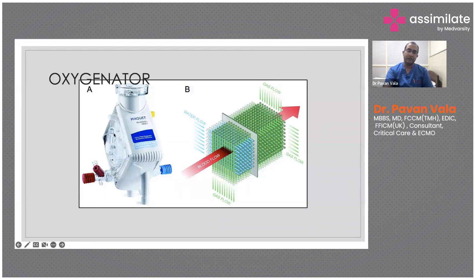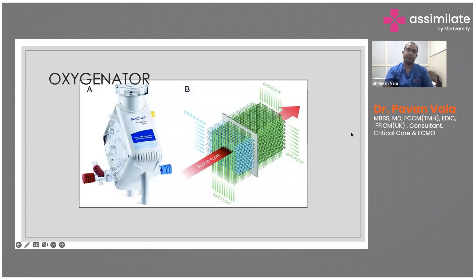The oxygenator is made of PMP — polymethyl pentene — a hollow fiber oxygenator. It looks like a dialysis cartridge but is a different material. Blood flows on one axis, gas flow on another axis, and water flow on a third axis to maintain temperature. This is what oxygenates and decarboxylates the blood.